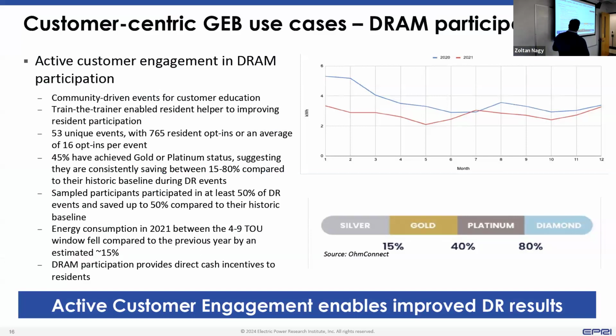And they, on average, about 70% of that community was able to get something of the order of 70% energy reduction through this platform. And more importantly, all of this capacity, the reduction in energy use, was being used to offset needs from the overall grid. So DRAM stands for demand response auction mechanism. This is a mechanism where capacity that is available by reducing loads at individual homes can be taken, and that excess capacity can be bid into the market to reduce the need for building new power plants. So if you did that, you're able to see that there is a tremendous reduction and advantage to that participation. Normally, you get about 1 to 2% participation in the DRAM market, whereas you're now getting about 15%, which is great.